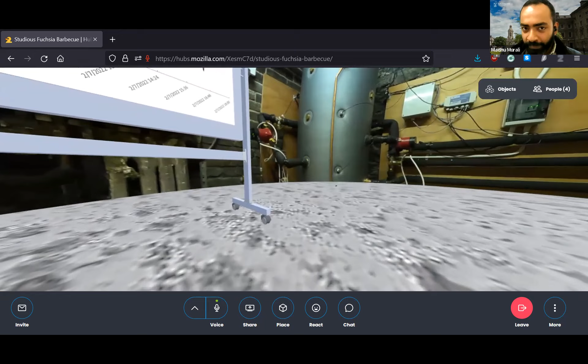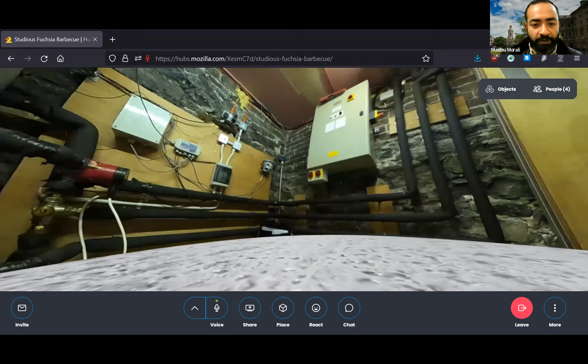Okay, so this is the control room of the cellar, and this is what Angus referred to as our buffer tank. You can see there's a pump over here to the left-hand side of it, and another pump to the right-hand side of it. What the pump on the right-hand side did was pump the water within the tank out to the heat exchanger up there, as you can see. It would go to the bottom of the heat exchanger, come out from the top after having absorbed all the heat from the wastewater, and come back into the tank from underneath.